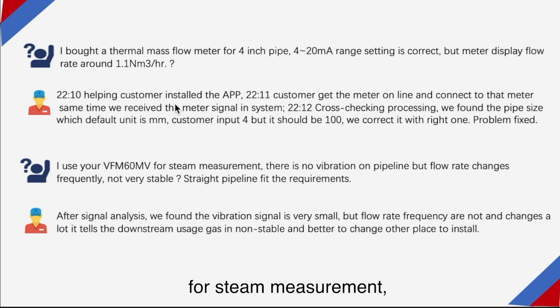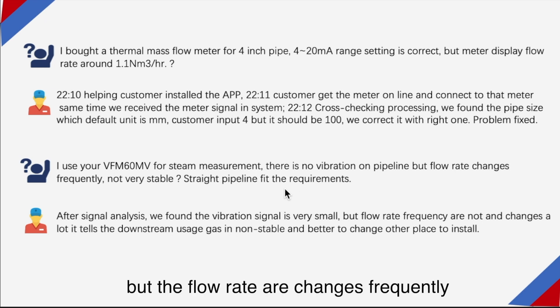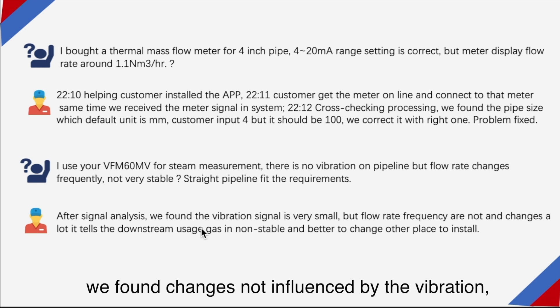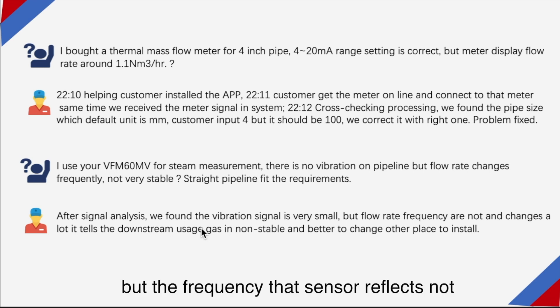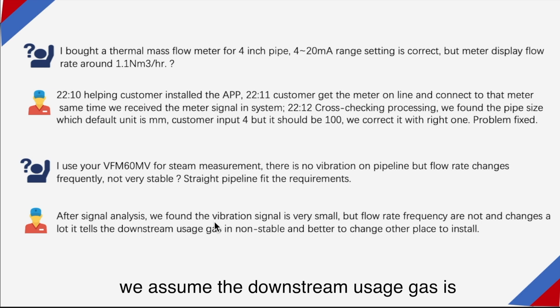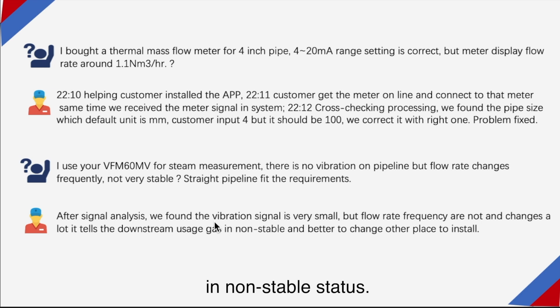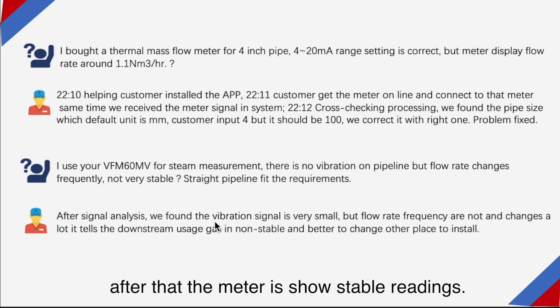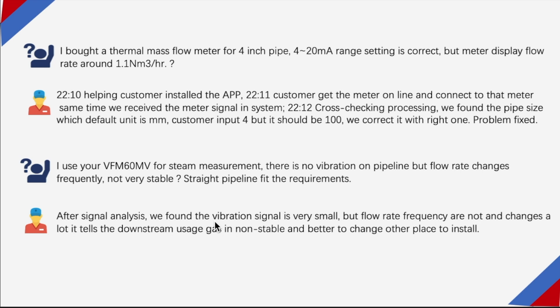We corrected it. For a second case involving a vortex meter for steam measurement, the customer provided enough straight pipeline but the flow rate was changing frequently. After remote signal analysis, we found the changes were not caused by vibration, but the frequency the sensor reflected was not very stable. From photos provided from the site, we assumed the downstream gas was in an unstable status. We recommended changing the installation location, and after that the meter showed a stable reading.